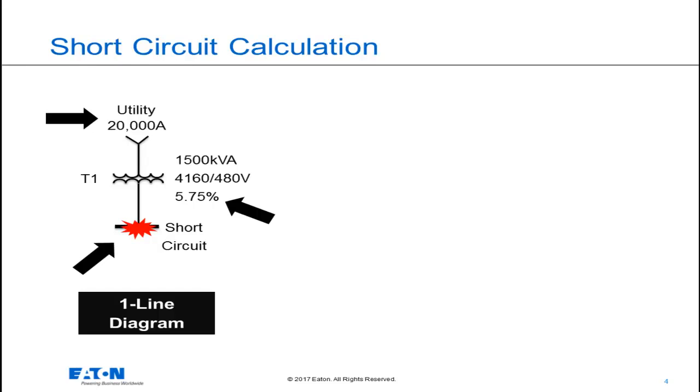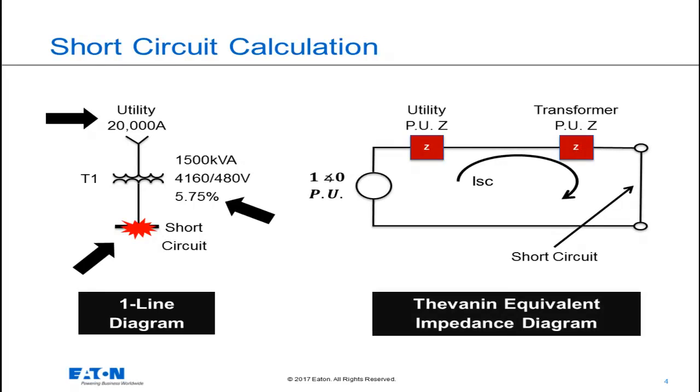This one-line diagram can be converted into a Thevenin equivalent, and that would be looking back from that short circuit to the utility. The two impedance values that we have there is the source equivalent impedance from the utility and the transformer percent impedance. Both of those are going to be placed in a per-unit format.